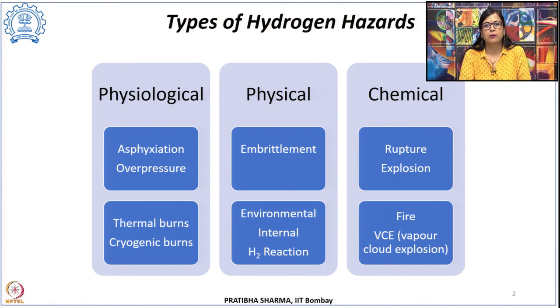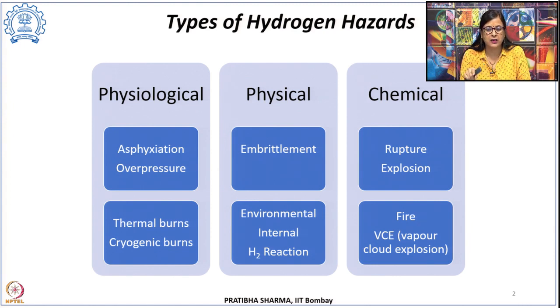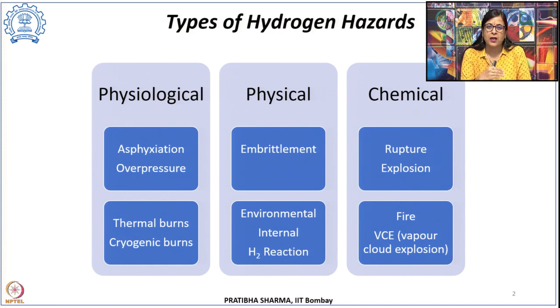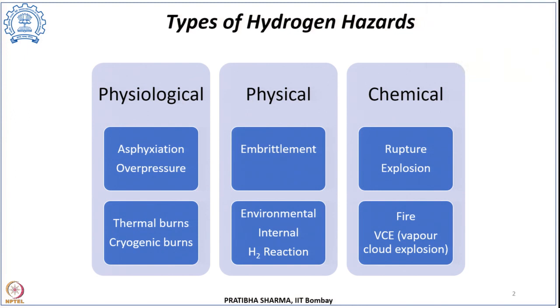Among the physiological hazards, if a person is present at either a hydrogen leak or at a hydrogen fire or explosion site, then because of the flammable mixture of hydrogen and air resulting in ignition and leading to fire, explosions, or leakages, that could cause severe injuries to the person. Other than direct injuries, it is also possible that hydrogen leak can displace oxygen if it is in a confined space, and that displacement of oxygen — if it reduces below 19.5% by volume — can lead to asphyxiation.